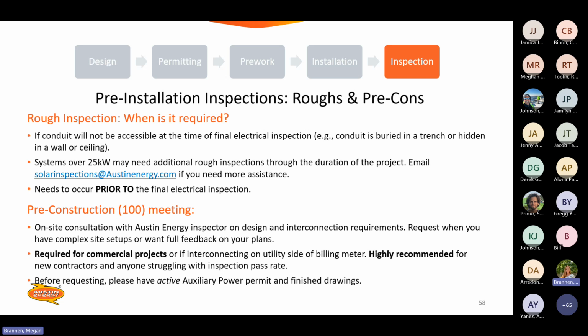All right, we talked about this a little bit already, but pre-install inspections include roughs and pre-cons. A rough inspection is required if any conduit is going to be covered up. Systems over 25 kW may need additional rough inspections throughout the duration of the project. So particularly if you're doing commercial and you've got a lot of trench work or a lot of things that are being covered up by walls, please do call for those rough inspections. And keep in mind that for residential roughs, you do not need to be present as long as we've got access to all of the equipment. So usually you can get those teed up.